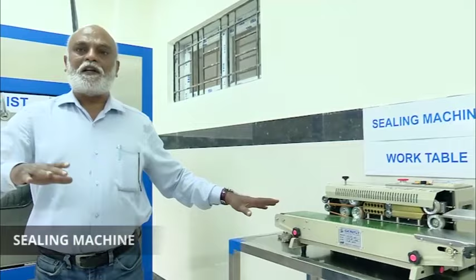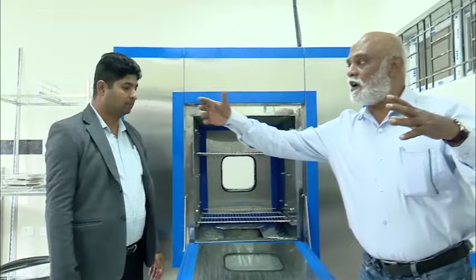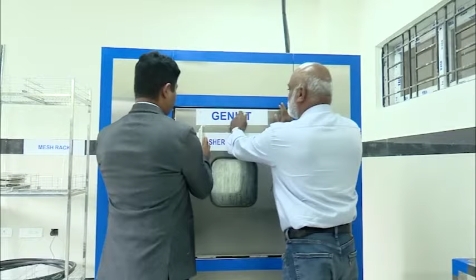And here is the washer disinfector. This is the instrument used for complete enzyme wash of all the instruments and the fabrics which come from the OT. First it will be washed and then put into the disinfectant. Then it will go to the autoclaving stage. So now we have again a storage rack with small, medium and large instrument trays. All the instruments are stored in this and given a sterilization of 134 degrees at 20 psi, high speed sterilization.